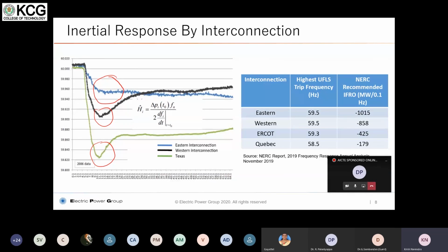And there is a NERC recommendation in North America called the Interconnection Frequency Response Obligation, IFRO, limits. And the limit for each one of the regions is stated here. And the negative sign is because of the generation loss. So 1015 megawatts per every 0.1 hertz. If the frequency drops by 0.1 hertz, you can lose only about 1015 megawatts in the Eastern region in order for it to operate stably. That's the meaning of IFRO.